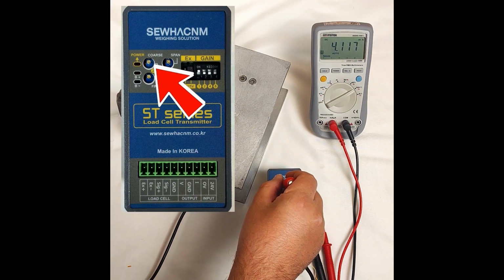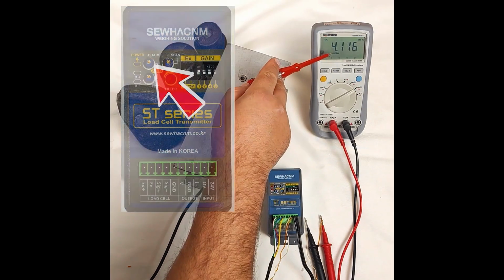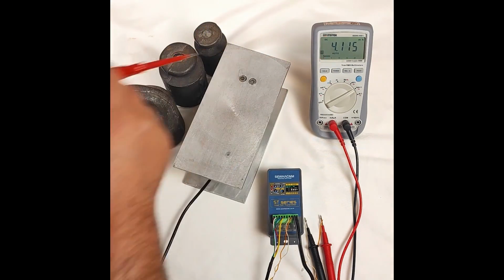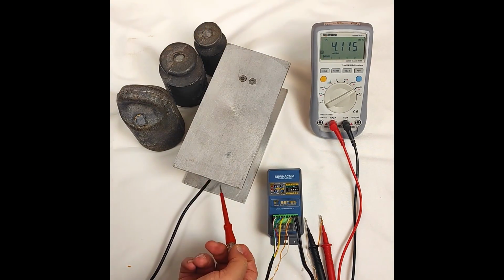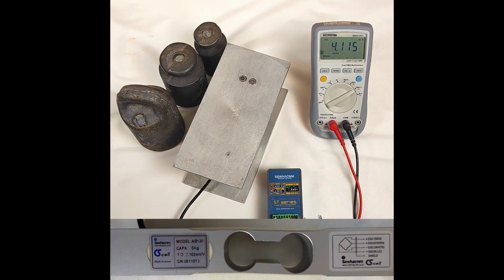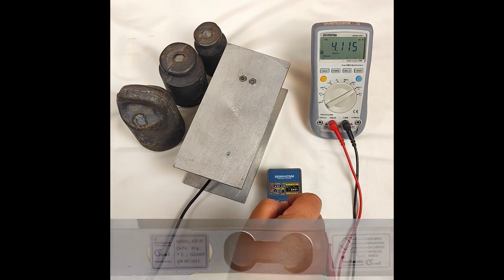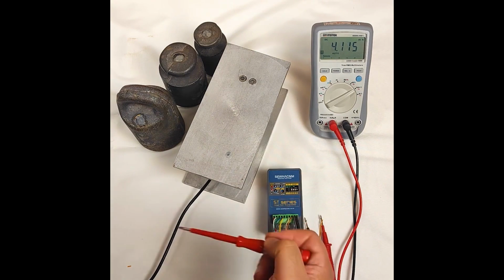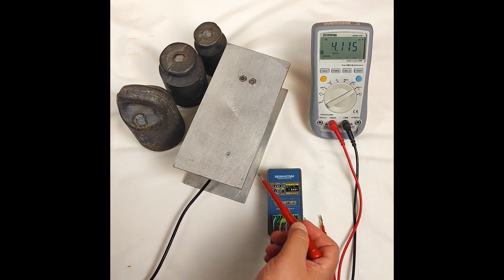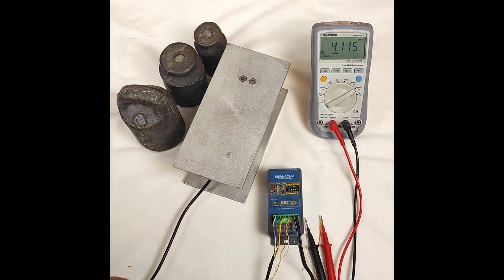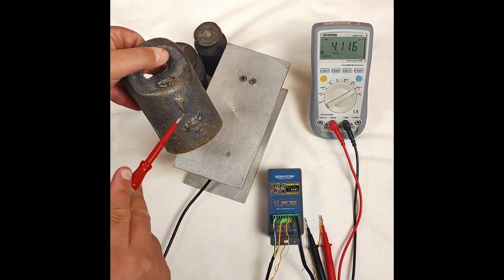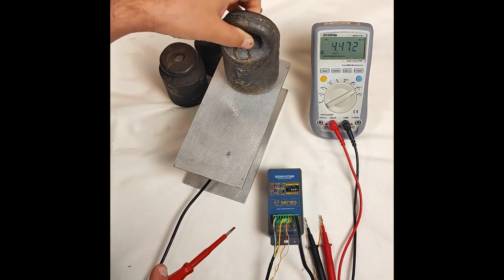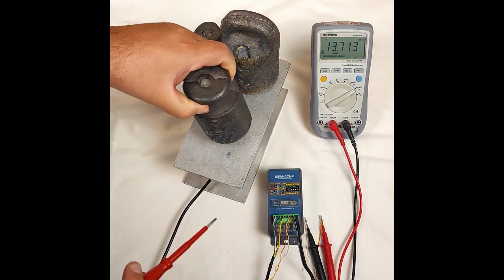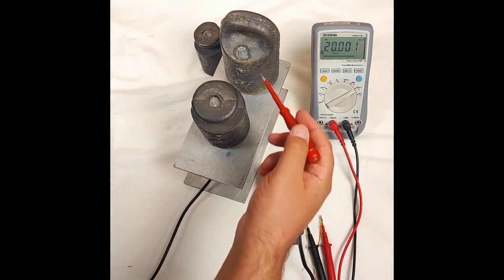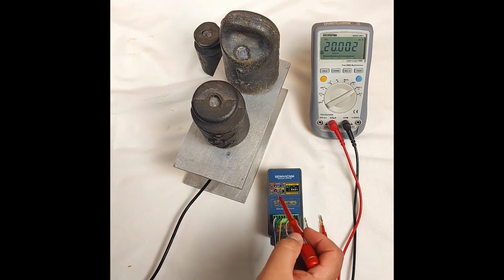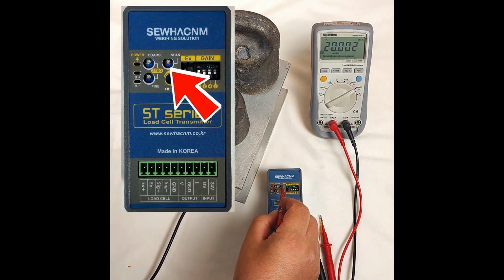There's a potentiometer here for zero adjustment. We turn this potentiometer until the multimeter shows a value of 4. The load cell we're using here has a capacity of 5 kilograms. This transmitter is analog, so for calibration we need the maximum load. Since it's 5 kilograms, we need a 5 kilogram weight. I place a 3 kilogram and a 2 kilogram weight, totaling 5 kilograms, on the load cell.